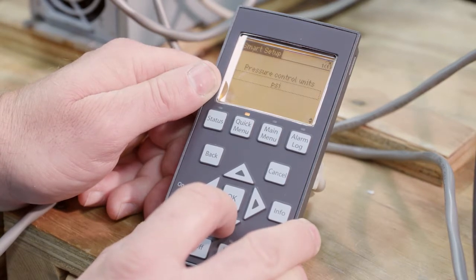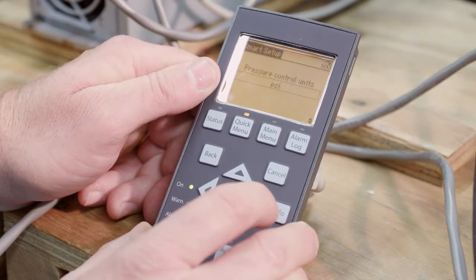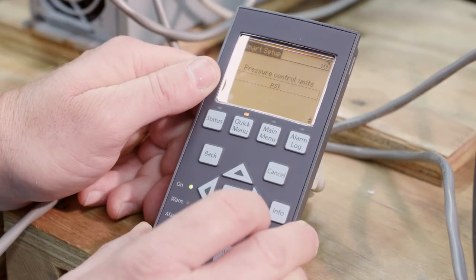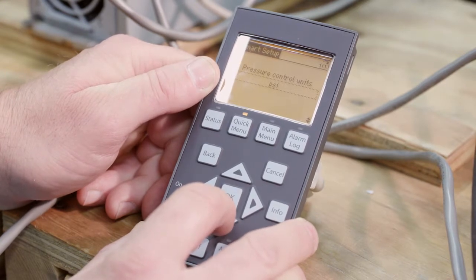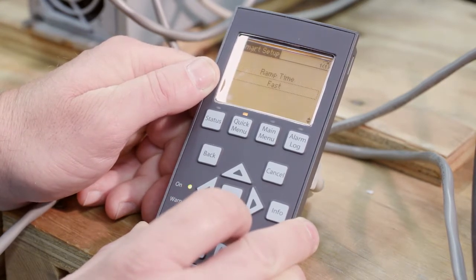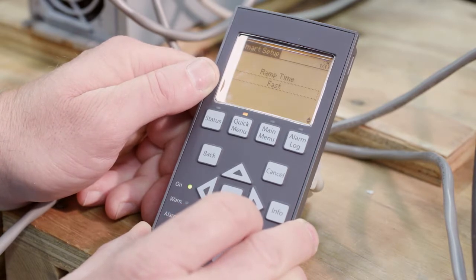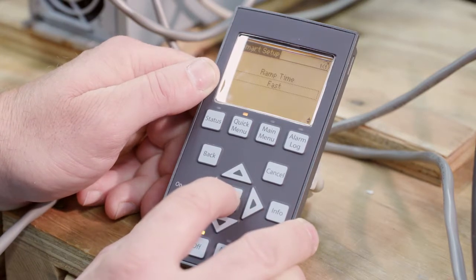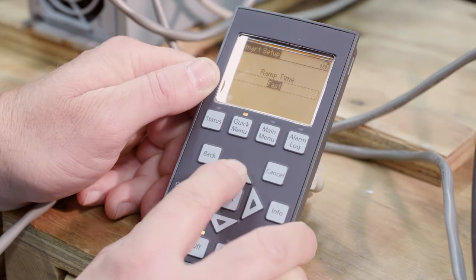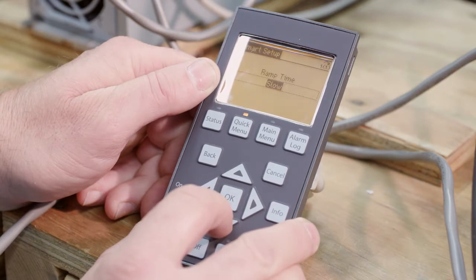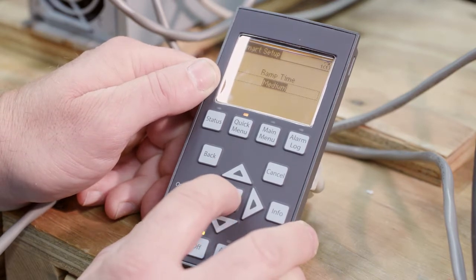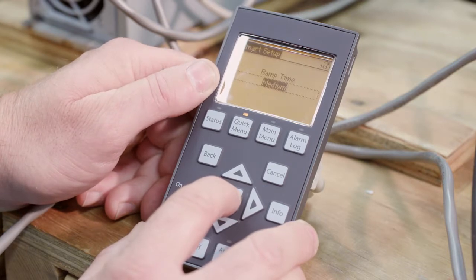So pressure control units, the display does not show the units, so you have to tell it what units you want it to be in. So we want to use PSI. So ramp time. One of the nice things about your quick setup, your smart setup, is you have some very simple options here for ramp time, fast, medium, and slow. And if you do not know, you can start with medium, and you can always go back and change your ramp time. So your ramp time is how quickly do you want your system to react based on your demand.